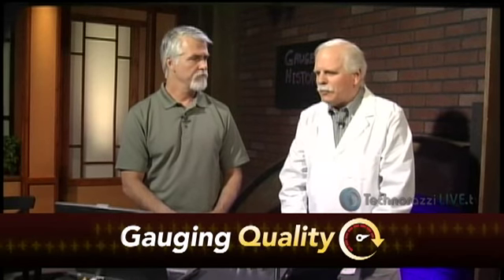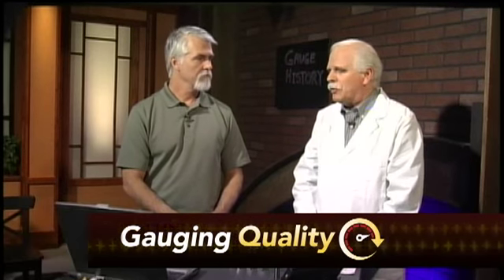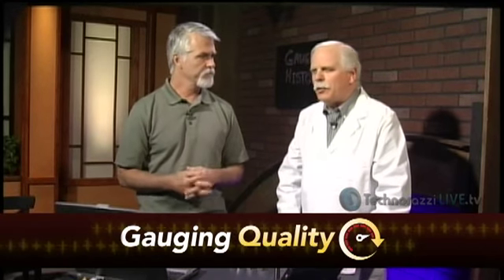Right. Well, there's a number of factors there. You can use a lot of these reports to do such things as gauge R&R studies. You can do wear analysis, as we said. You can do stability. What about interval, being able to see whether you're on the right interval or not? That's a good point. We get that asked quite a bit. What's the proper interval? Usually, the basis of the question is financial. It's less expensive if they calibrate it every 3 years rather than every year.